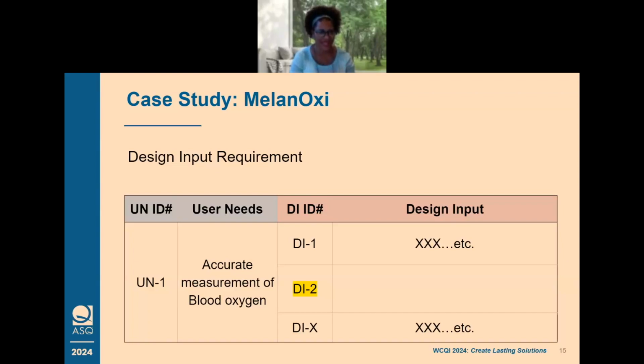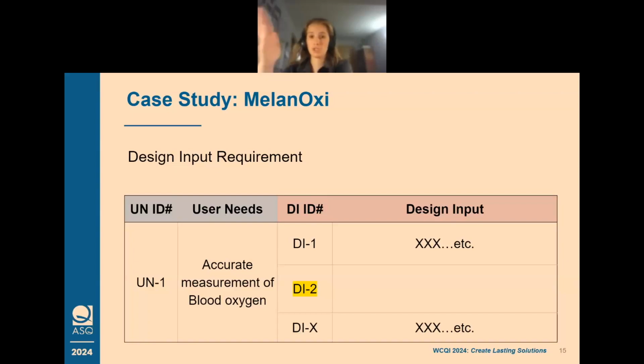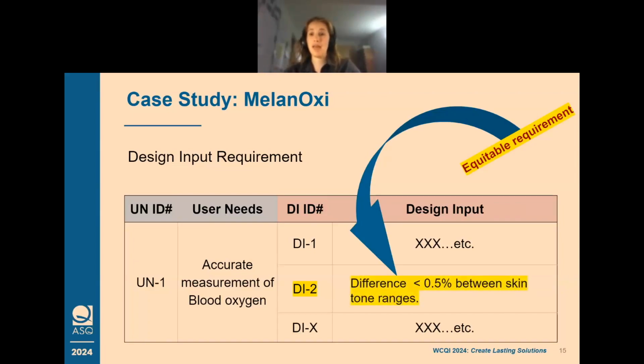So DI, we're not going to list all of them, but we're going to focus on DI2, the equitable requirement. So, like Lorian mentioned, we're just going to be tracing one thing throughout the entire matrix, and it's going to be sequential. So, pay attention. In order to get an accurate measurement of blood oxygen, an example of a design input that's equitable would be that the difference is less than 0.5% between skin tone ranges to ensure that you're truly getting that safety and efficacy regardless of the levels of melanin in people's skin.